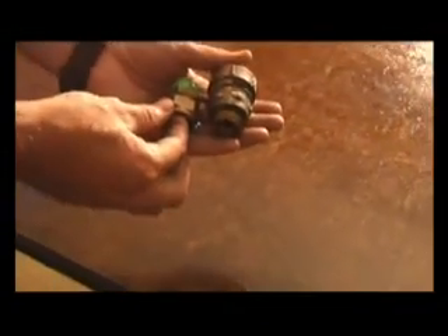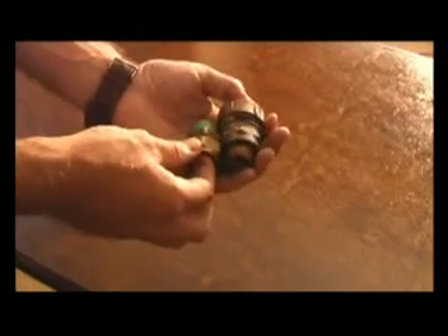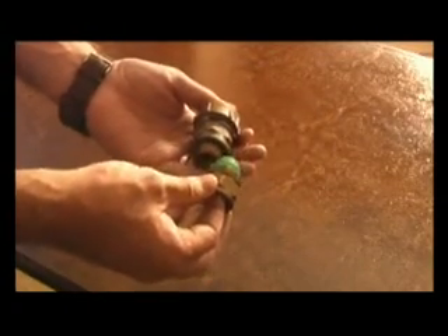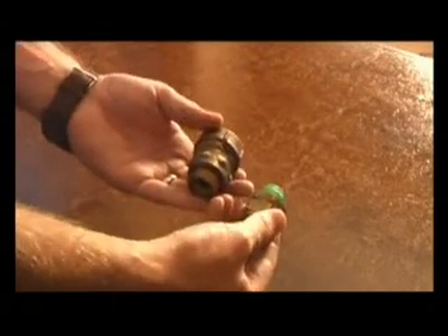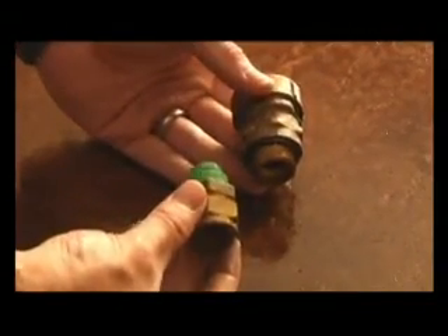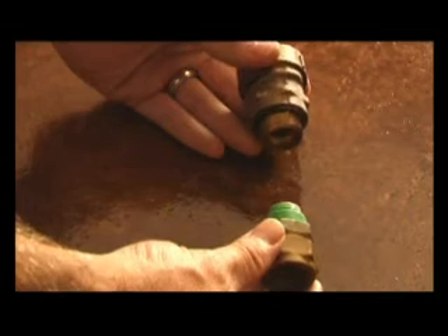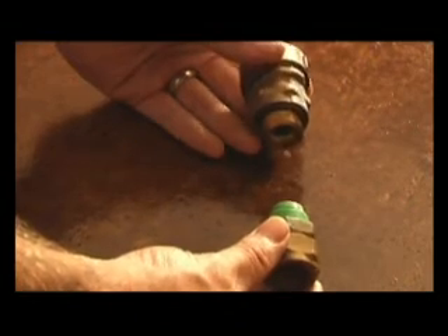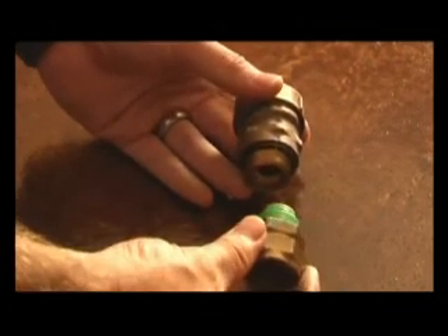A vacuum breaker is needed on the hot and the cold side of the water supply to the geyser and the hot water out from the geyser. These are two vacuum breakers made by two different manufacturers. On the cold water side of the geyser, the vacuum breaker needs to be on a T above the level of the water of the geyser to alleviate the siphonage of the water out of the geyser when the mains is cut off.